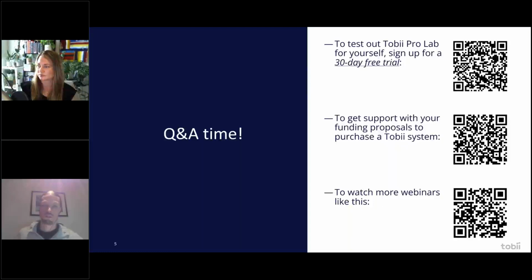Yeah, sure. During the design process in Tobii Pro Lab, you can send events at the onset time of your stimulus. This works for videos, for example, pictures, or text elements even. In order to do so, your computer needs to have a parallel port. Alternatively, we support certain USB to TTL converters, and this is the best way to do it. This is especially important if you want to synchronize with EEG, depending on the experiment that you are doing, with high demands on timing, right?